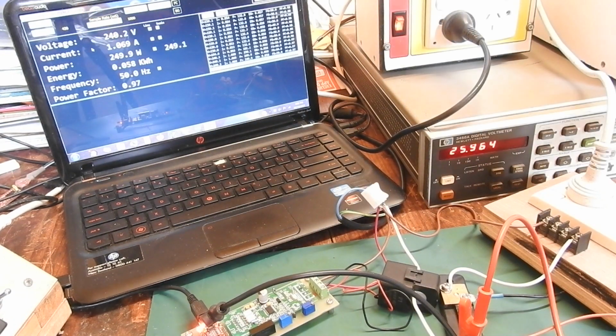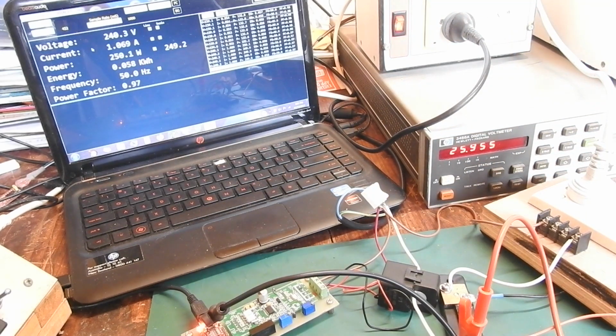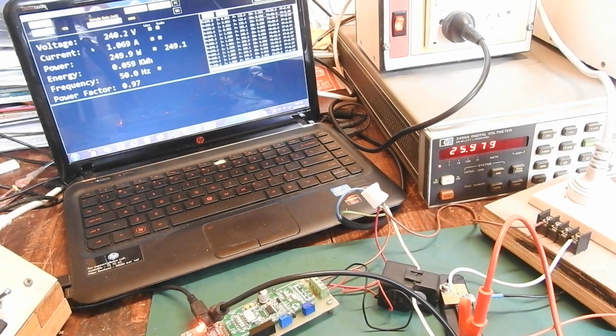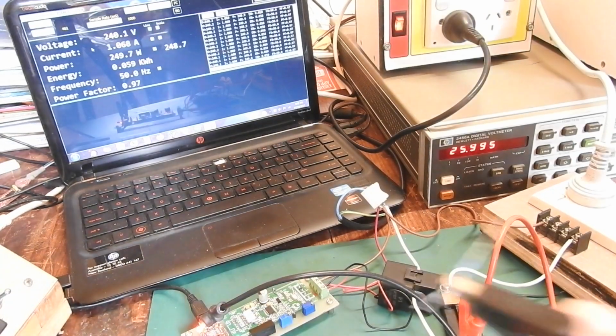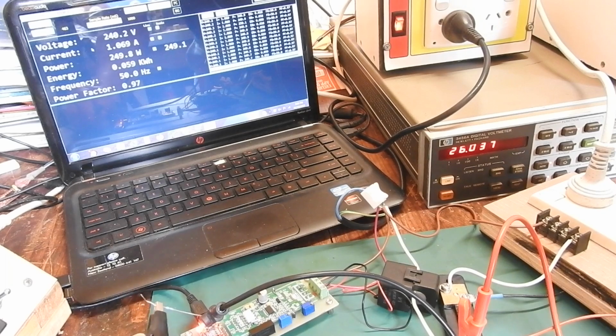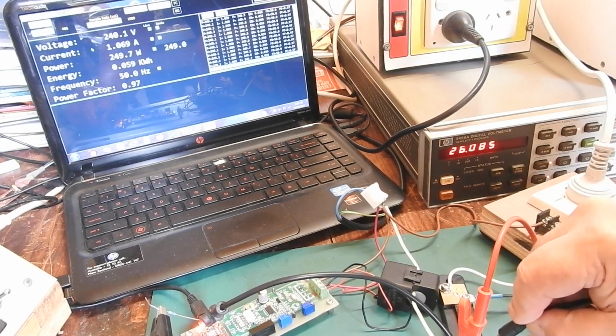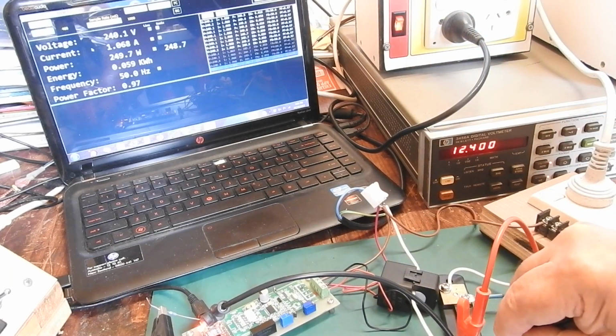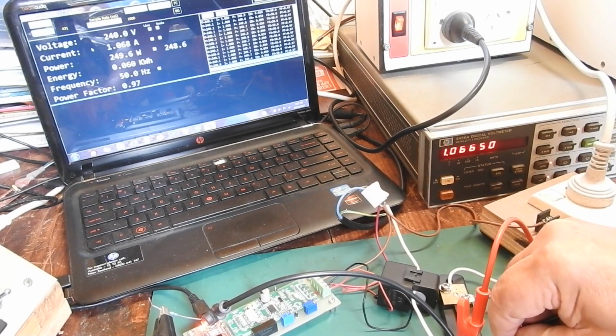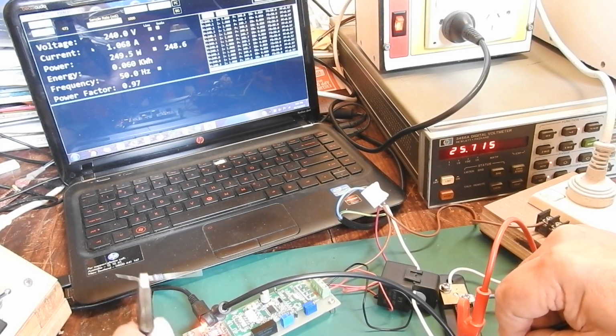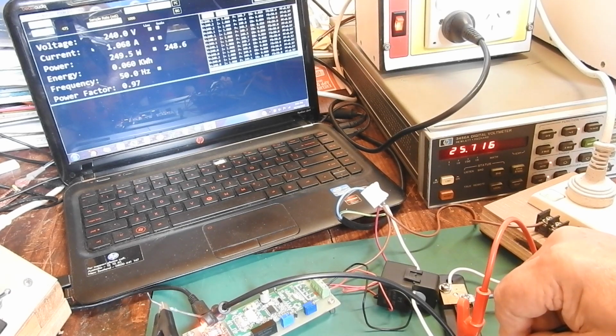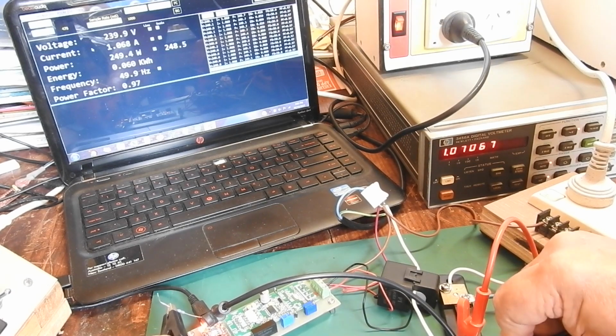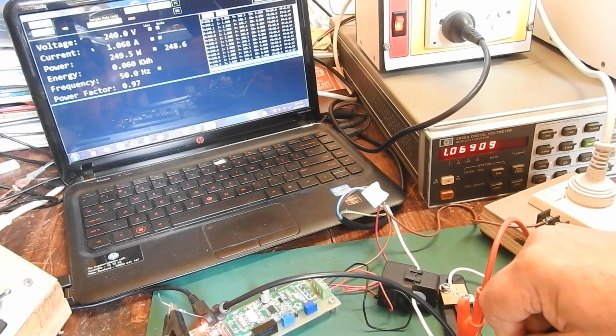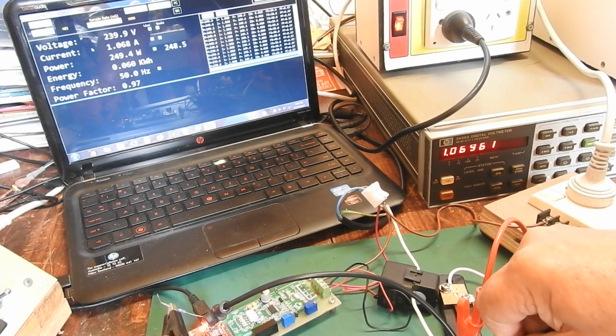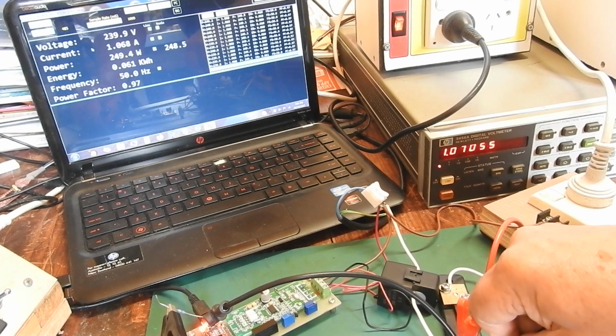Now, is that really dangerous or not? Well, if I just grab some resistors, 39K, first thing I saw, and put one of those between earth and the active, that voltage drops down to 1. So if 39K can reduce that 26 volts down to 1 volt, then it's got no power behind it, it's just capacitive coupling, and it really is isolating. At least that's my theory.